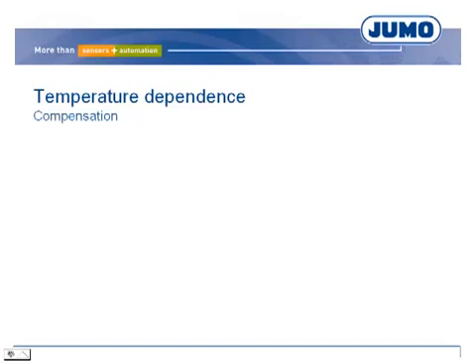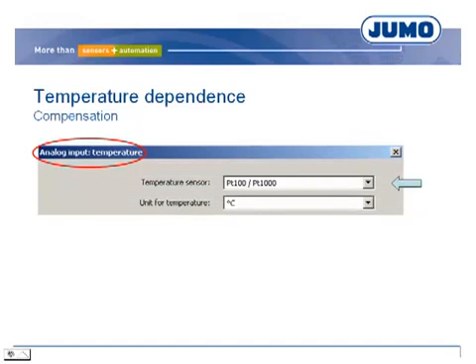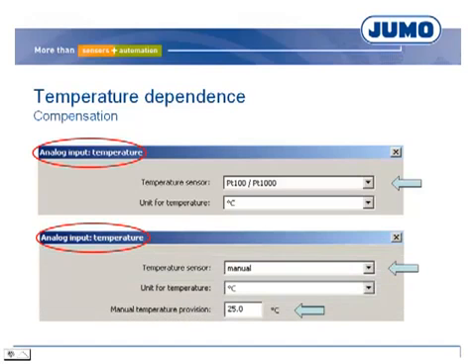The slope of the characteristic depends on the temperature. There are two possibilities for compensation. A resistance thermometer measures the temperature of the medium and the transmitter compensates the deviation. When the temperature of the solution is stable, this temperature can be set on the transmitter.